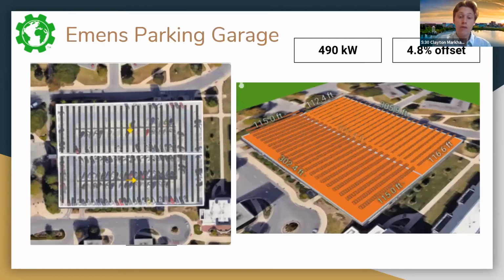This is our proposed 0.5 megawatt system on the parking garage. The pros of this system are that you don't have to worry about drilling into water lines or other risks you'd have with putting PV on academic buildings, nor covering up green space as with a ground mount system. We have half the panels facing east and half facing west, so this PV would have max output at different times of day than our other south-facing installations.